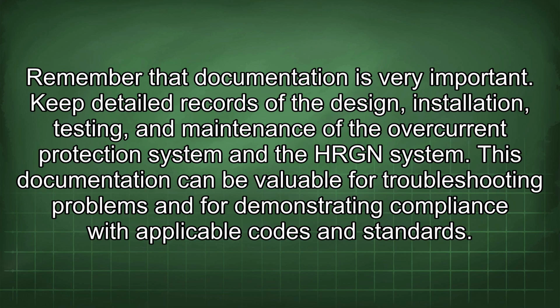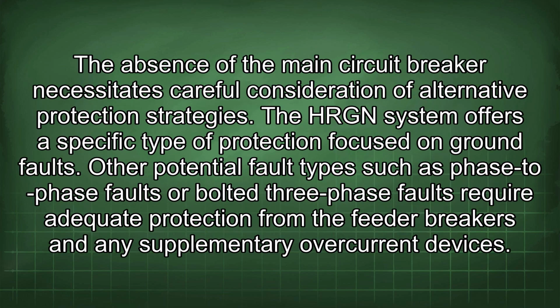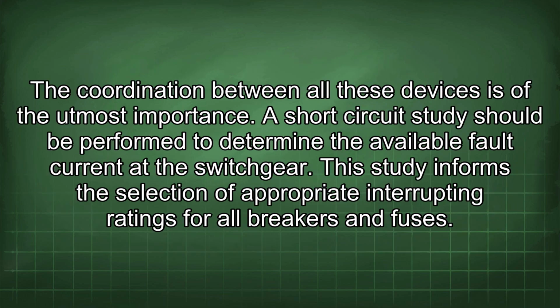Remember that documentation is very important. Keep detailed records of the design, installation, testing, and maintenance of the overcurrent protection system and the HRGN system. This documentation can be valuable for troubleshooting problems and for demonstrating compliance with applicable codes and standards. The absence of the main circuit breaker necessitates careful consideration of alternative protection strategies. The HRGN system offers a specific type of protection focused on ground faults. Other potential fault types such as phase-to-phase faults or bolted three-phase faults require adequate protection from the feeder breakers and any supplementary overcurrent devices. The coordination between all these devices is of the utmost importance.